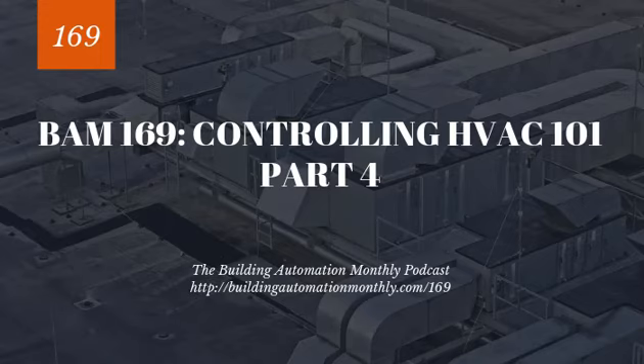And last thing you want to realize about boilers is that lead lag is different than chillers. With chillers, we just simply switch over. We call it a day. With lead lag, since we have slow warm up and low fire rate and high fire rate, the amount of time to switch from one boiler to another is a little bit longer depending on the boiler. All right, so with that being said, we've got some core concepts down.